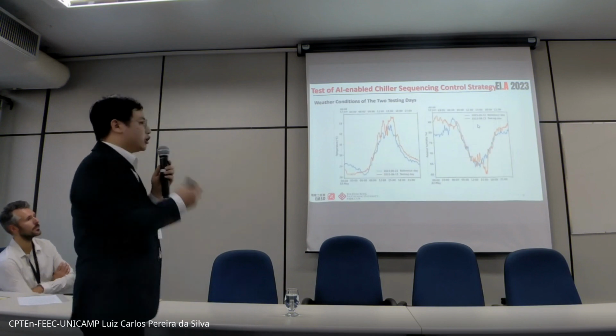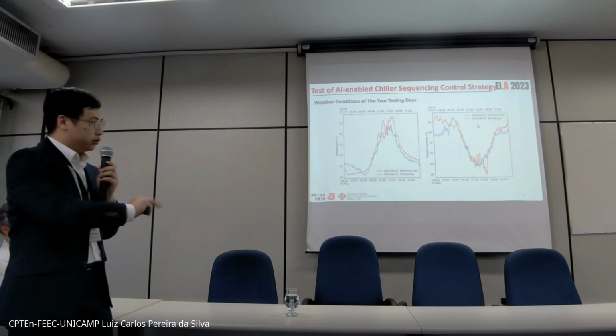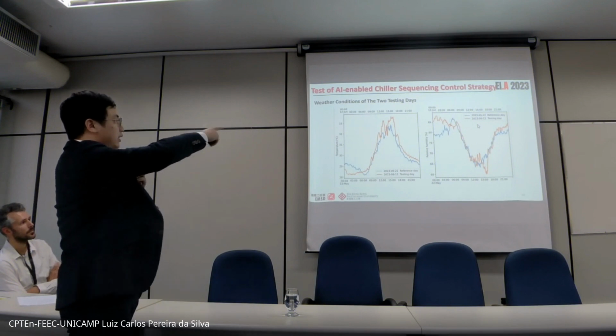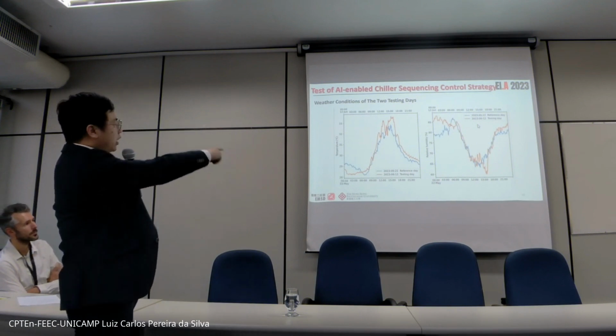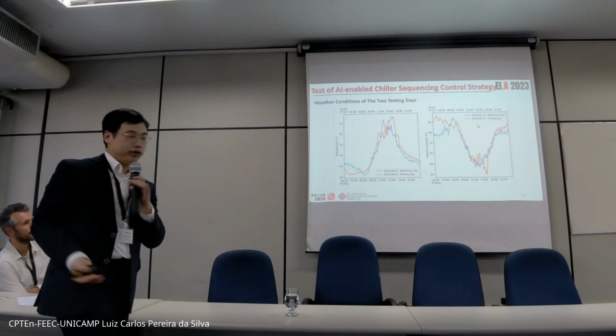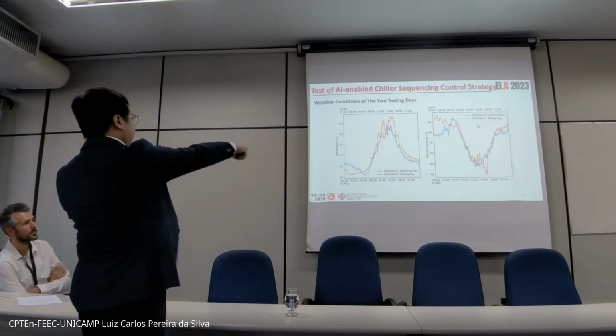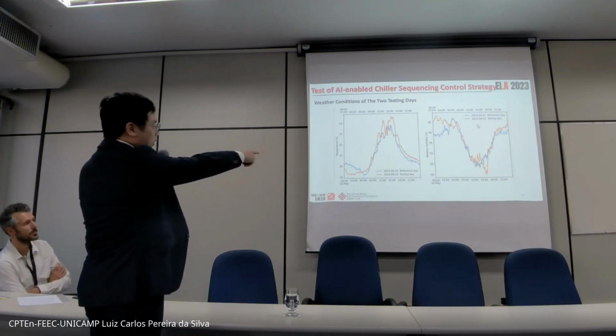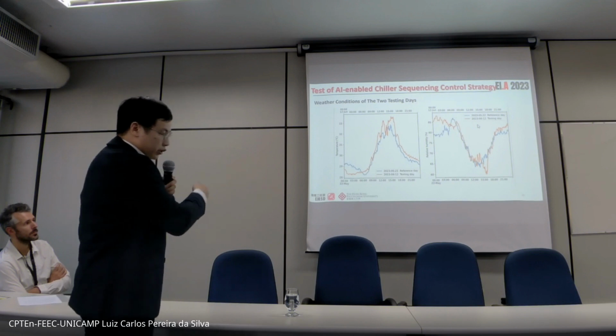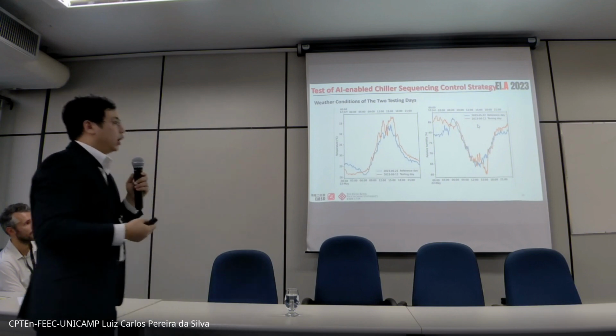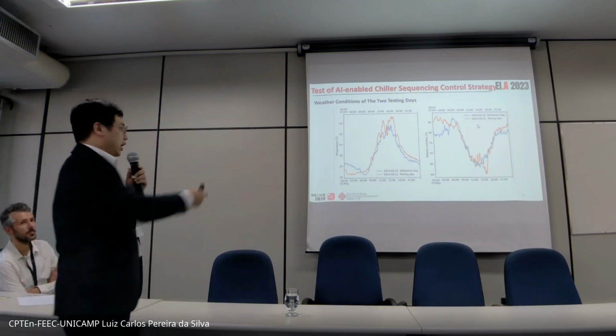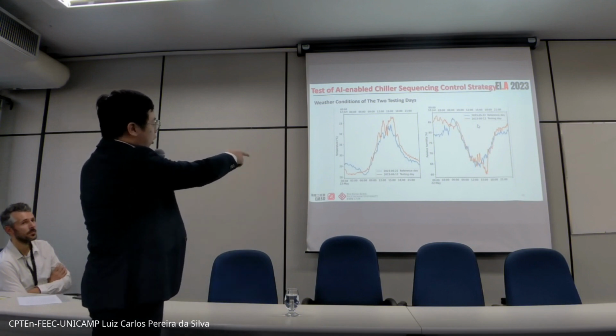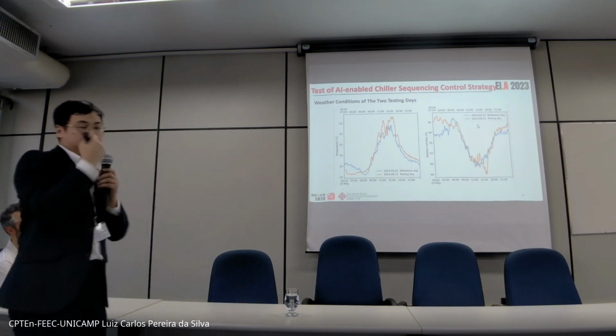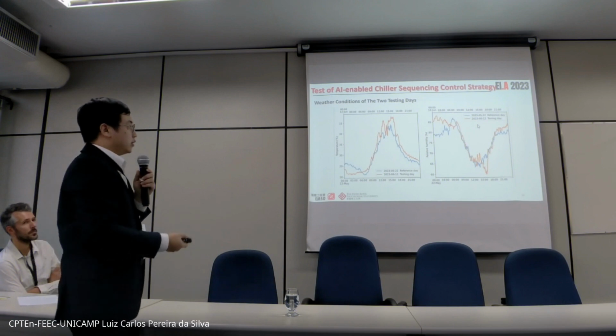We ran the test for several days and chose 2 testing days with similar weather conditions to compare results. The blue line represents the reference days, using the traditional control strategy, and the orange line represents the testing days using cooling load prediction-based sequencing control.